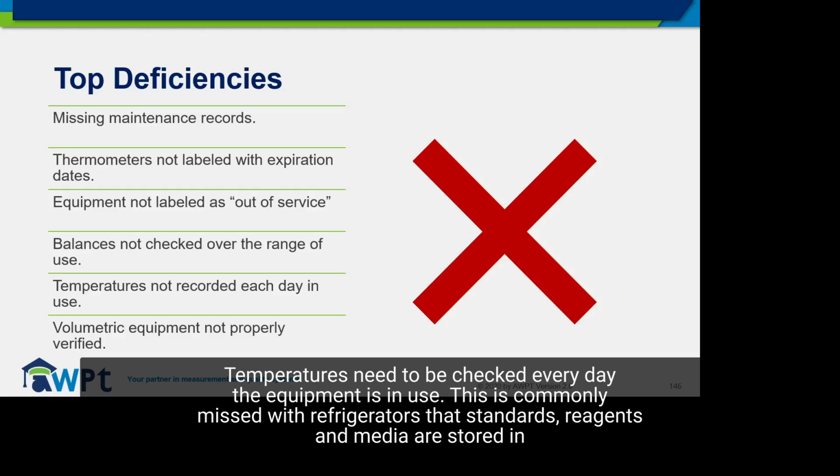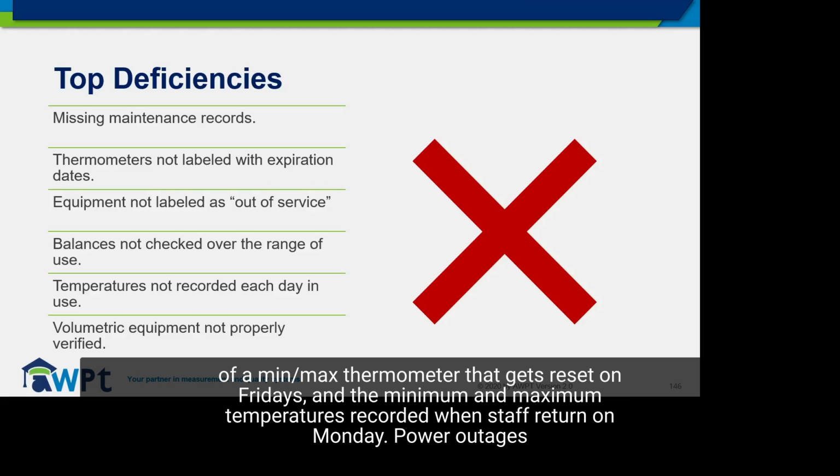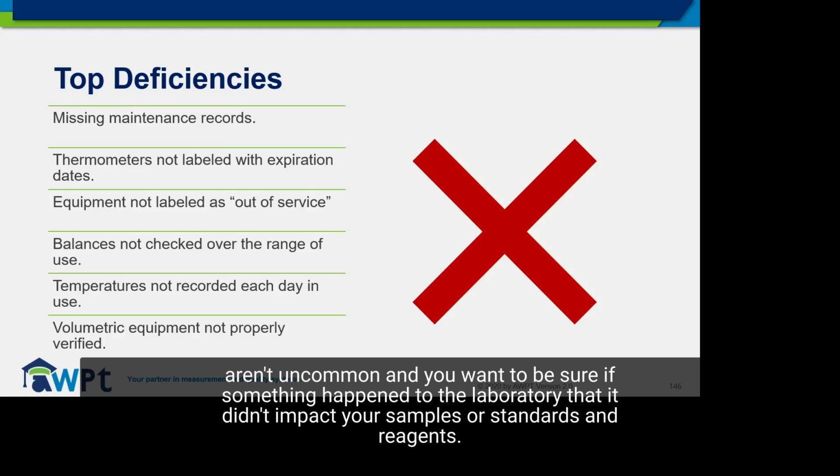Temperatures need to be checked every day the equipment is in use. This is commonly missed with refrigerators where standards, reagents, and media are stored, and BOD incubators that run over the weekends when the staff may or may not be in the laboratory. A simple fix is the use of a min-max thermometer that gets reset on Friday and the minimum and maximum temperatures recorded when staff return on Monday. Power outages aren't uncommon, and you want to be sure if something happened at the laboratory that it didn't impact your samples or standards and reagents.